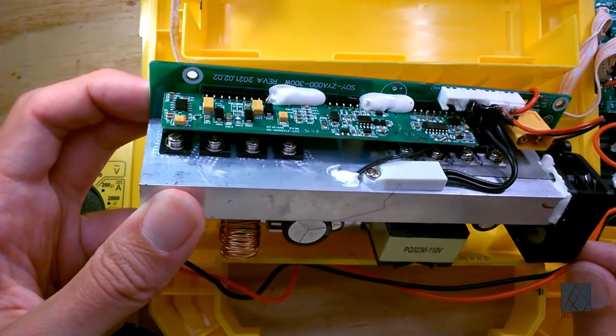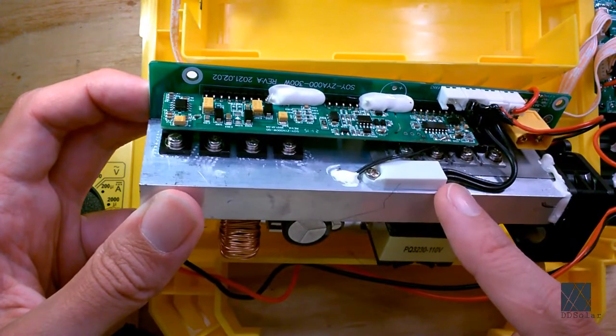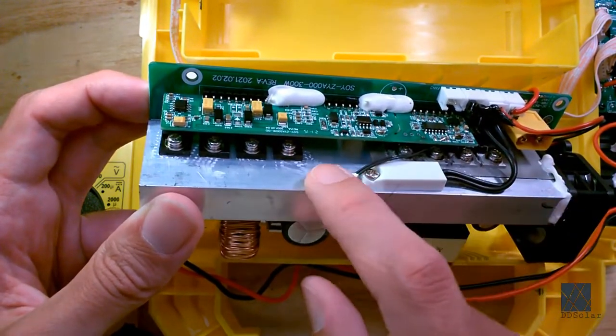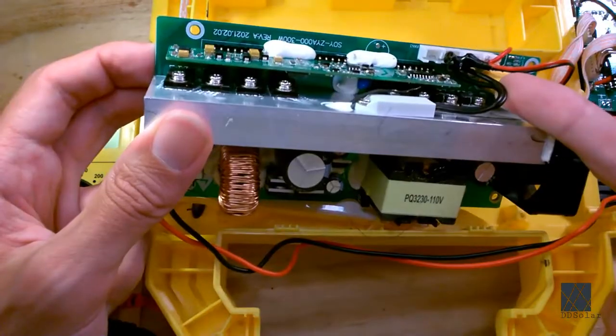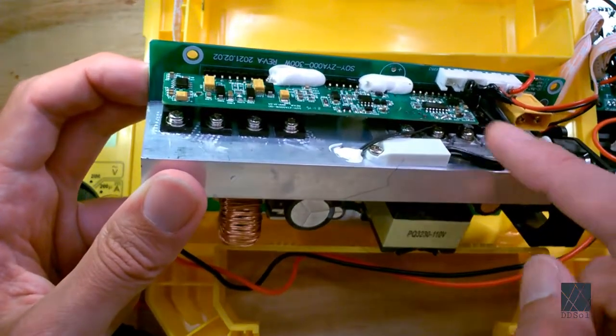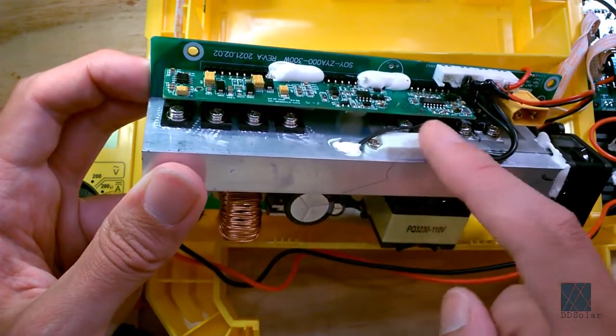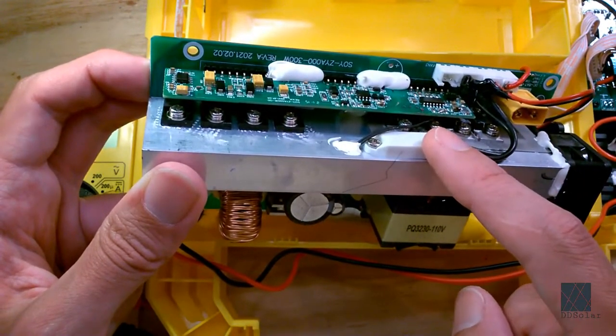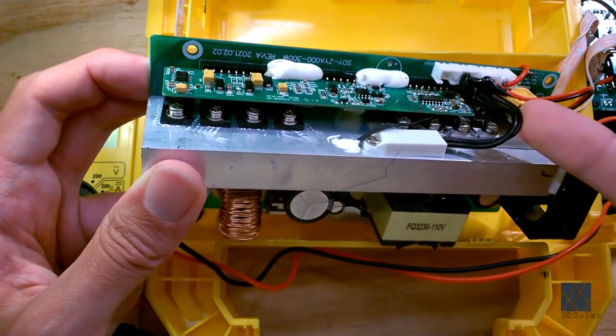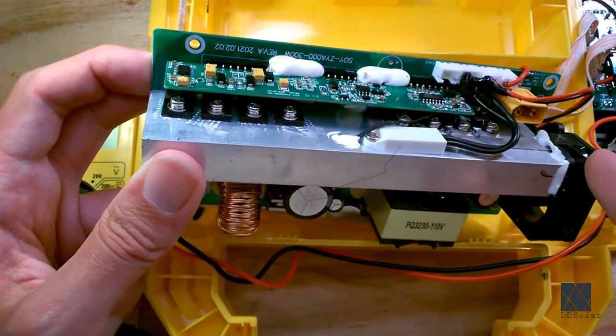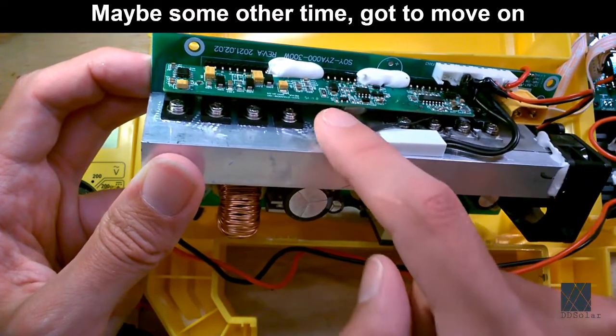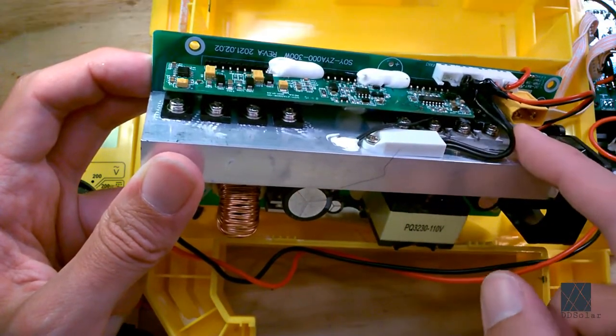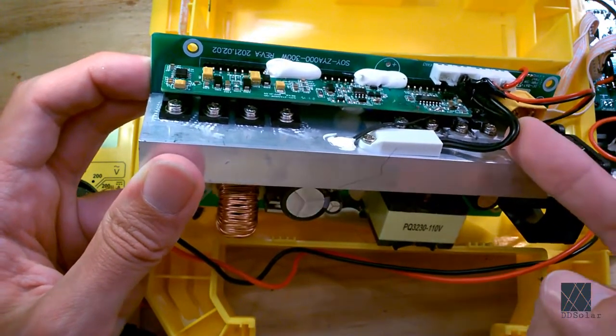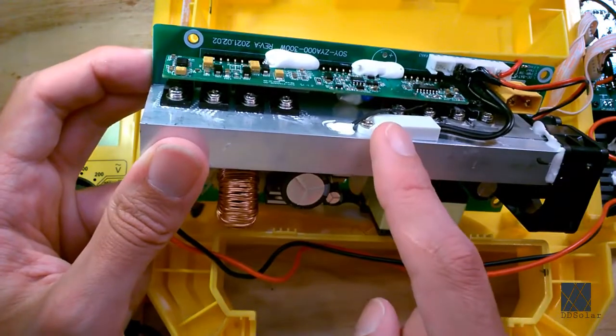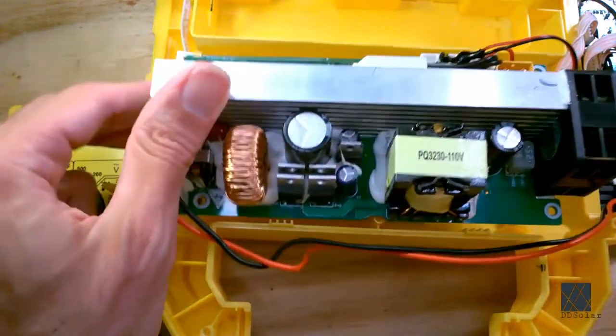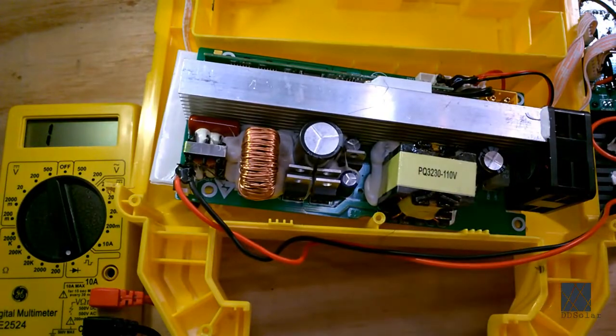Now, I did not overlook that there are 2 temperature probes here. I'm actually kind of scratching my head. Looks like a temperature probe here, but there's also one right here, and I do not know why they have 2. Now what I'll tell you is these go bad all the time. It's quite possible that this inverter thinks it's overheating because these temperature probes are not giving the correct reading. I can't be bothered right now to unglue and unscrew these and tear them out of the board and measure their resistance, look up the part numbers and see what the resistance should be, because my guess is they're probably working just fine, just like the diodes, and it really is just a problem with this transformer. So maybe later I'll look for a new one, see if I can find it.